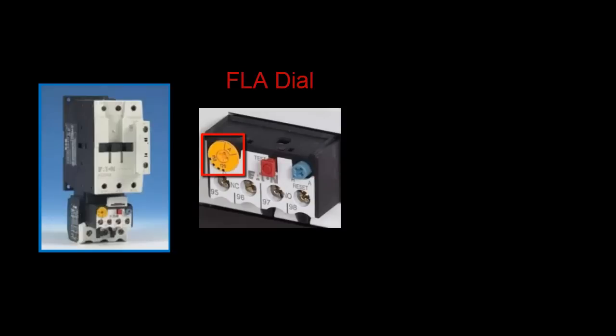This is where you define how much current the motor must draw for it to be considered an overload condition. This dial allows you to select between manual and automatic reset, and also serves as the reset button. And this is a trip test button. Then you have these two built-in contacts, a normally open and a normally closed.